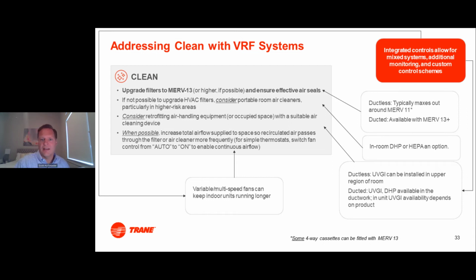When we're looking at adding an in-room portable air cleaner, you might consider an in-room HEPA. One technology we're looking at is a newer technology called dry hydrogen peroxide. I'll hit on that shortly. When you're talking about cleaning the air that's coming to the space, again, we have some recommendations there based on ASHRAE to use things like UVGI or dry hydrogen peroxide. And then the last but not least, making sure you've got enough airflow. Again, with variable multi-speed fans, we can keep those units running longer and keep that air flowing through the filter to actually be cleaning it.